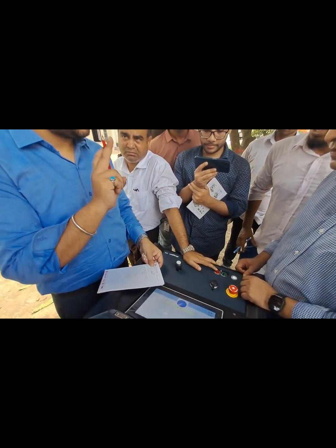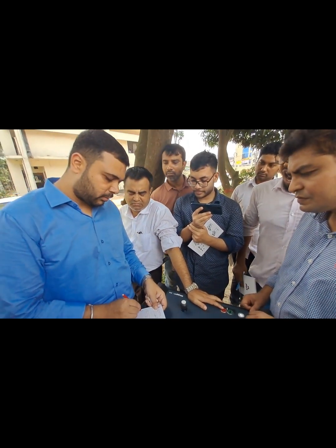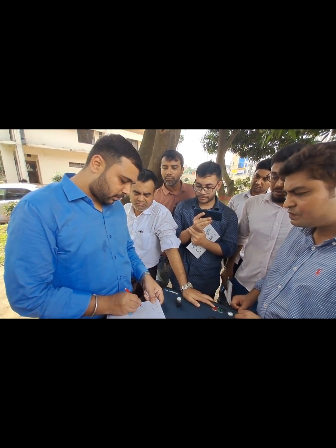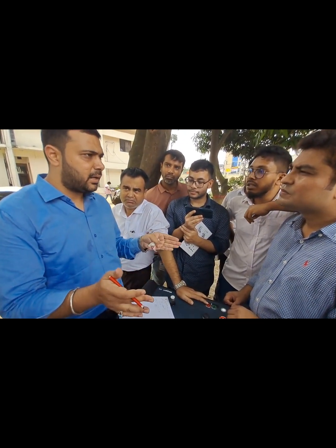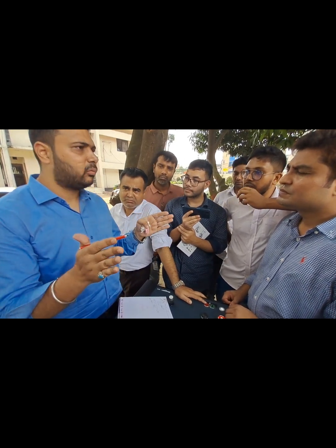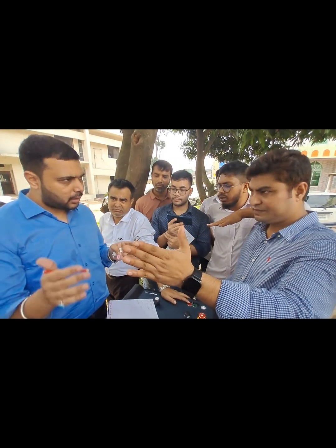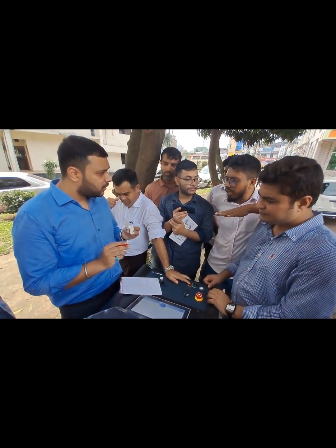Okay, now I am coming to my second step, that is DC Hipot. In DC Hipot, we used to just act as a withstand test, to see whether the cable can withstand this voltage or not. If it is withstanding, we declare that it is a healthy cable.